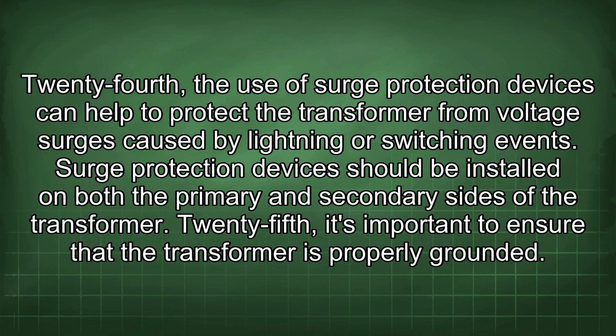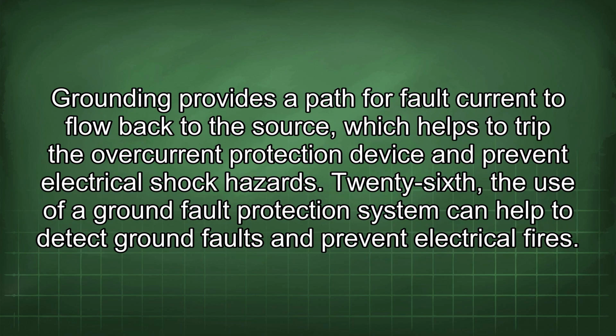24th, the use of surge protection devices can help to protect the transformer from voltage surges caused by lightning or switching events. Surge protection devices should be installed on both the primary and secondary sides of the transformer. 25th, it's important to ensure that the transformer is properly grounded. Grounding provides a path for fault current to flow back to the source, which helps to trip the overcurrent protection device and prevent electrical shock hazards.